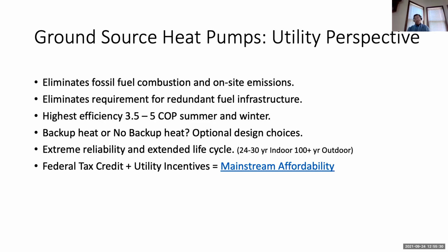The extreme reliability of geothermal systems comes from the fact that all we're doing is moving energy, we're not managing ignition and burn temperatures. We have over a 24, 25-year rated life through ASHRAE, the American Society of Heating and Cooling Engineers. The life of the machine itself is that 24.7 years. I frequently change out systems that are 38 years old, because again, all we're doing is moving energy, not managing high temperatures and pressures. The external portion of a geothermal or ground source heat pump now has a rated life of over 100 years. Again, that's polyethylene material fused together through a fusion process.